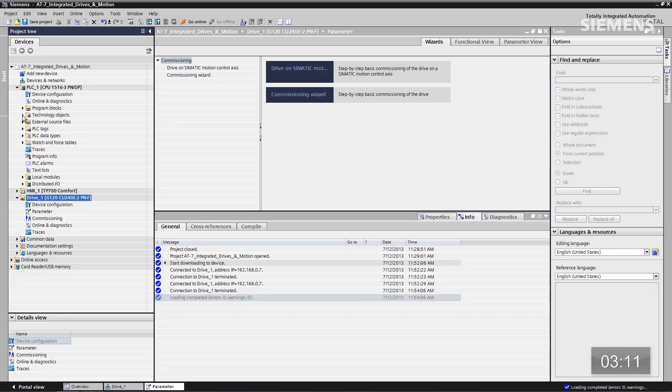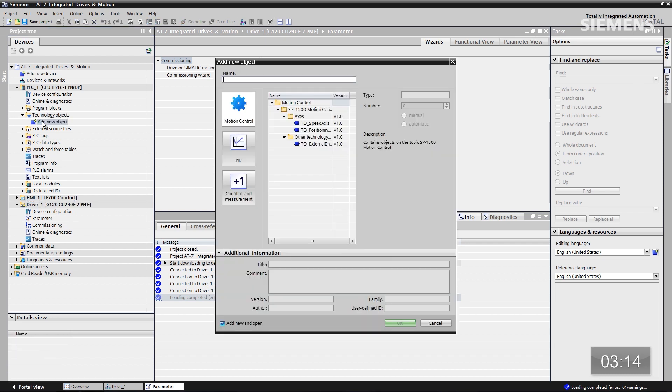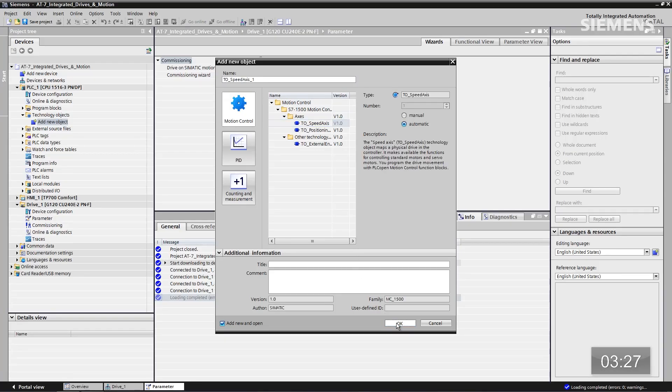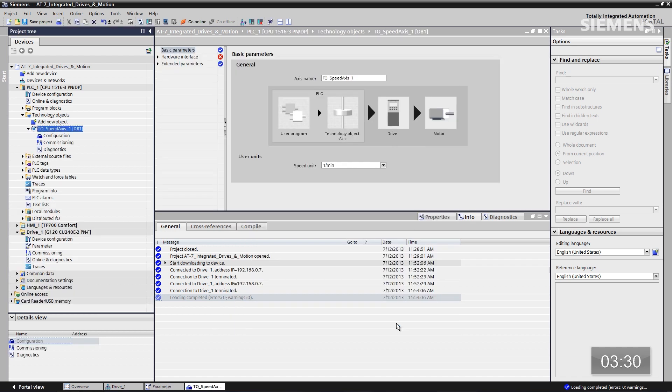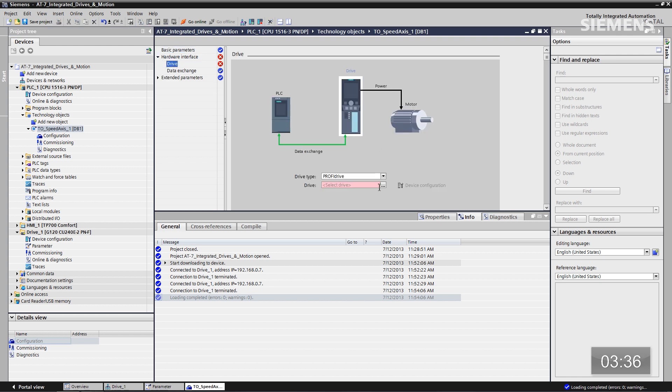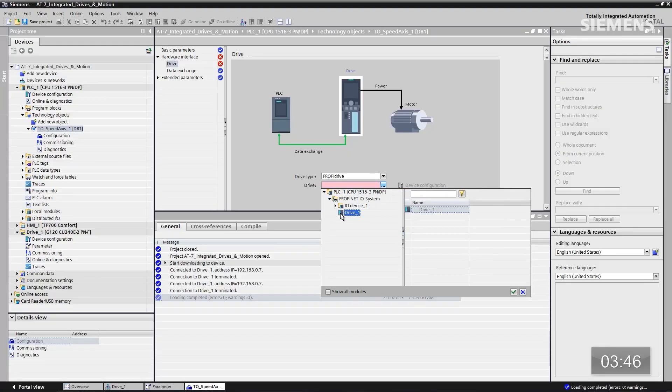So how about setting up the motion for this application? I want to come over to the tree structure and go to Technology Objects and double-click Add New Object. A pop-up box appears, and our first option is motion control to set up a speed axis, positioning, or external encoders. For this application, we're going to use speed axis. Give focus to speed axis and click OK. Now I can input data for this motion application — I want to choose the hardware interface and drive. Clicking that button lets me navigate to our hardware configuration section and find the G120 we just parameterized. There it is — click OK. That's all we need to do for the speed axis.